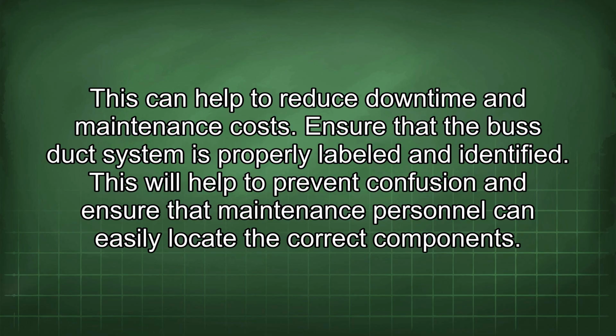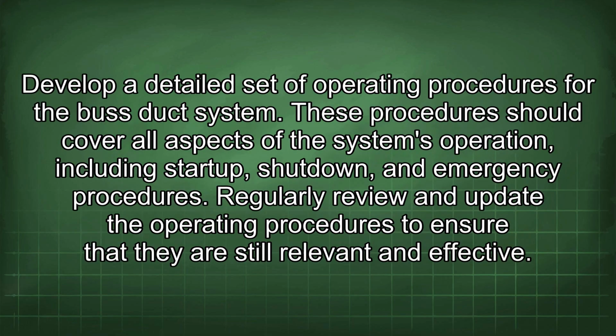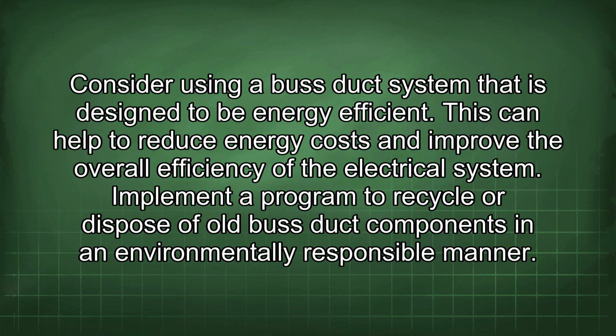Ensure that the bus duct system is properly labeled and identified. This will help to prevent confusion and ensure that maintenance personnel can easily locate the correct components. Develop a detailed set of operating procedures for the bus duct system. These procedures should cover all aspects of the system's operation, including startup, shutdown, and emergency procedures. Regularly review and update the operating procedures to ensure that they are still relevant and effective. Consider using a bus duct system that is designed to be energy efficient. This can help to reduce energy costs and improve the overall efficiency of the electrical system.